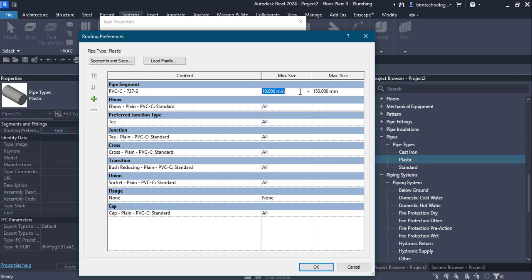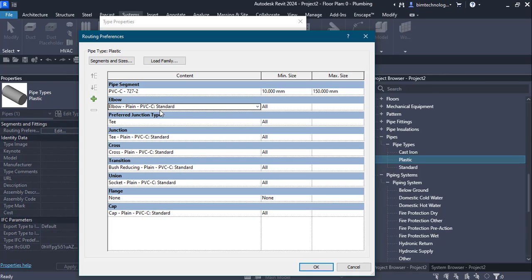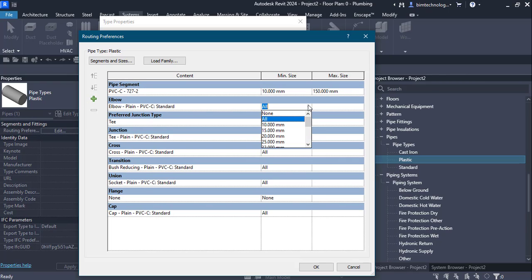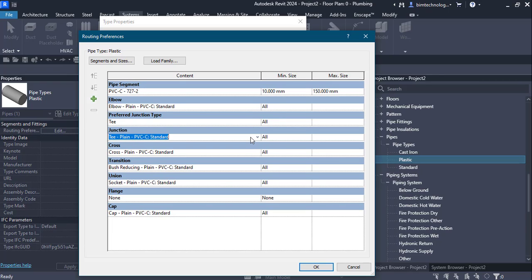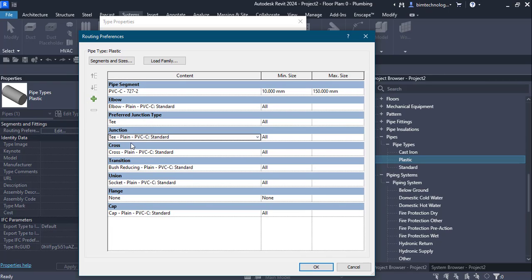For elbows, you can select from the drop-down list — in this case it is elbow plain PVC standard, taking all sizes with no minimum or maximum. The preferred junction type can be T or tap; by default it is T for all sizes. If the junction is T, you can specify the type — it can be branch 90-degree plain CI, but by default it is plane PVC. The cross would be PVC standard, the transition is bush reducing plain PVC standard, the union is a socket plain, and the cap is cap plain PVC standard.